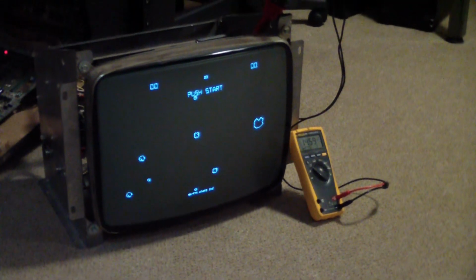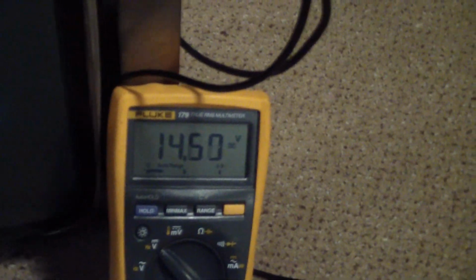And I'm going to let this thing run for a few hours. If we look at the HV voltage, well, the high voltage, we are at 14.6 kilovolts. 14.5 is nominal, and that's holding. It'll probably go up a little bit as time goes on, but yeah, there you have it.